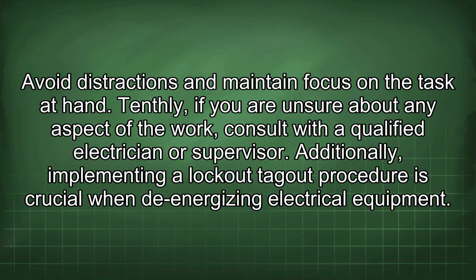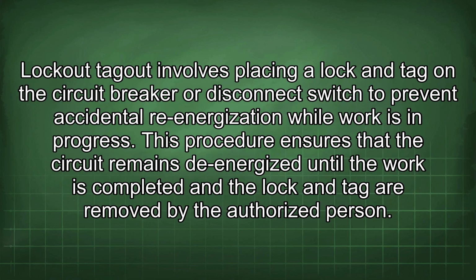Additionally, implementing a lockout-tagout procedure is crucial when de-energizing electrical equipment. Lockout-tagout involves placing a lock and tag on the circuit breaker or disconnect switch to prevent accidental re-energization while work is in progress. This procedure ensures that the circuit remains de-energized until the work is completed and the lock and tag are removed by the authorized person.